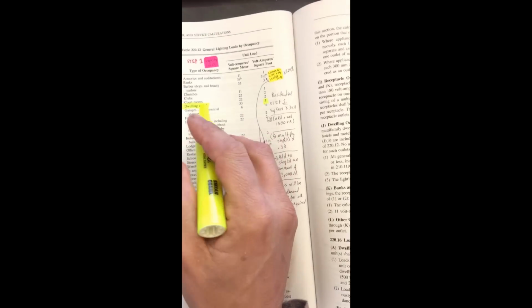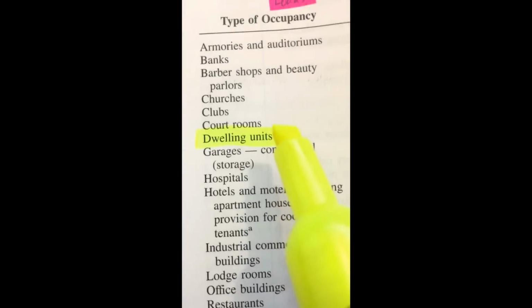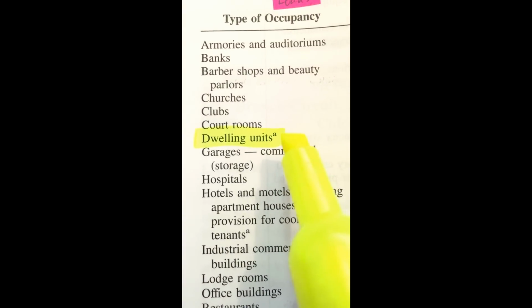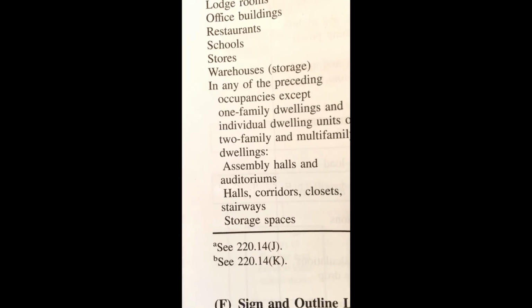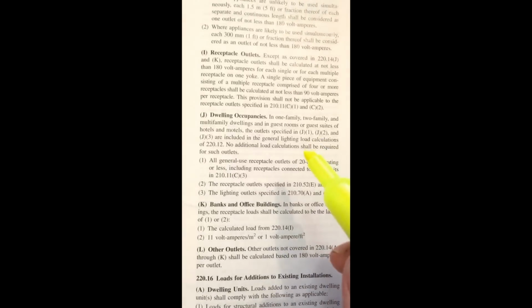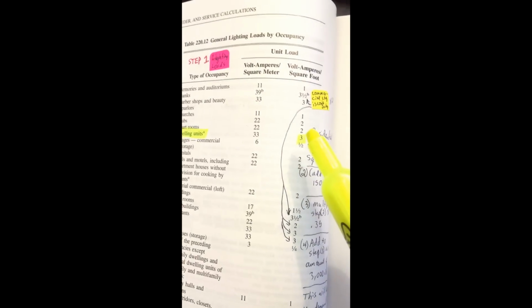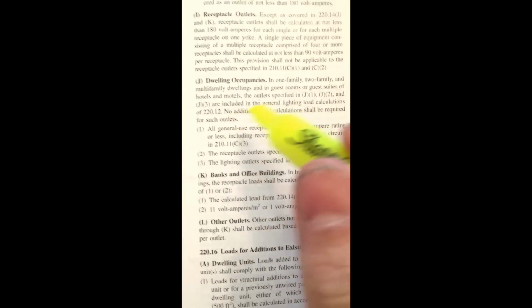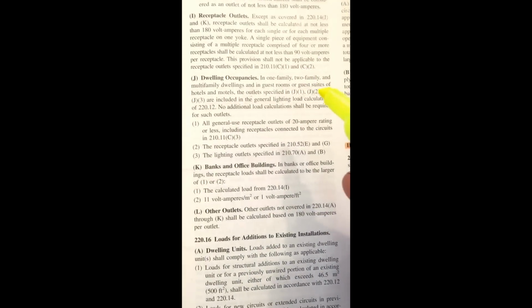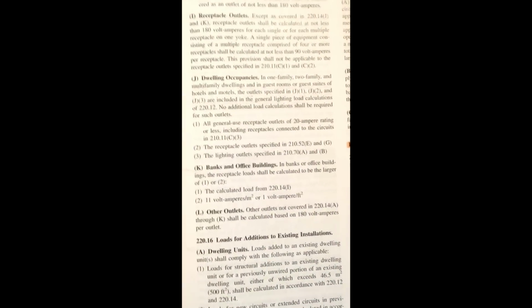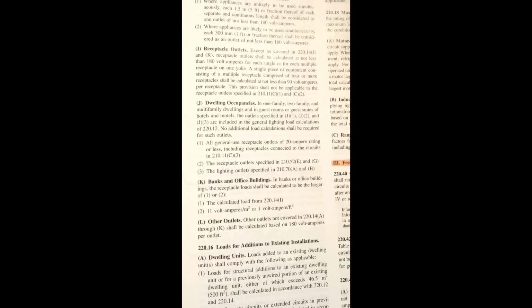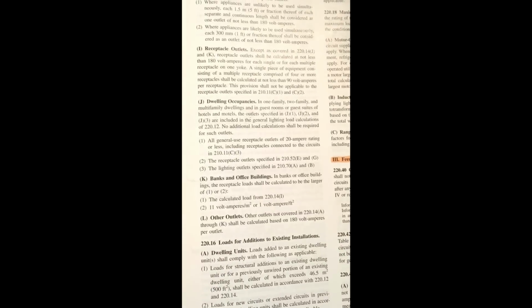Now that little letter A down here, right next to the end of the label, corresponds with a note down at the bottom of the table that just says 220.14(J). Well, 220.14J on the next page over here just simply says that this number here, which is the 3 volt amps, actually already includes all of the 20 amp, what we call general purpose. In other words, they're not specific circuits that are calculated for items such as your kitchen or the laundry room, but these are just the plugs in the bedroom, the living room, the hallway, stuff like that.